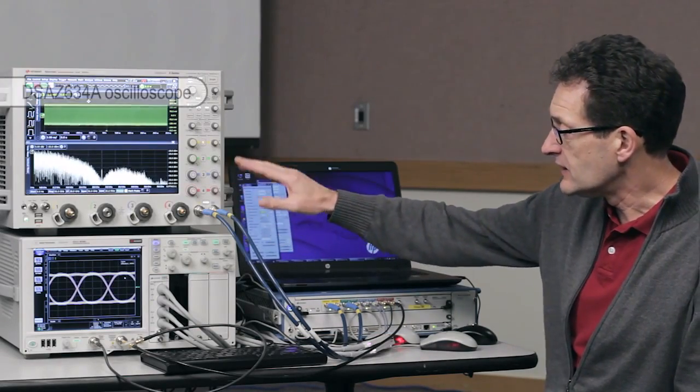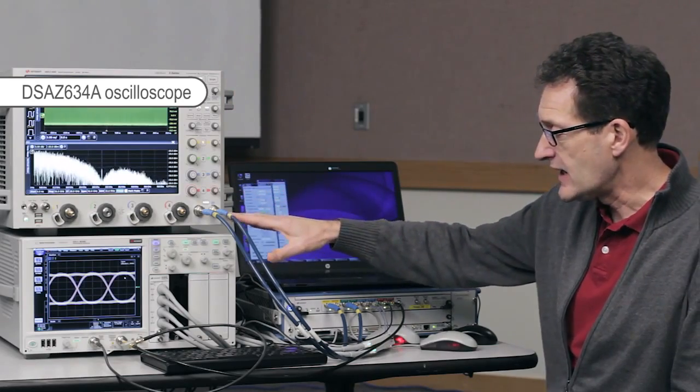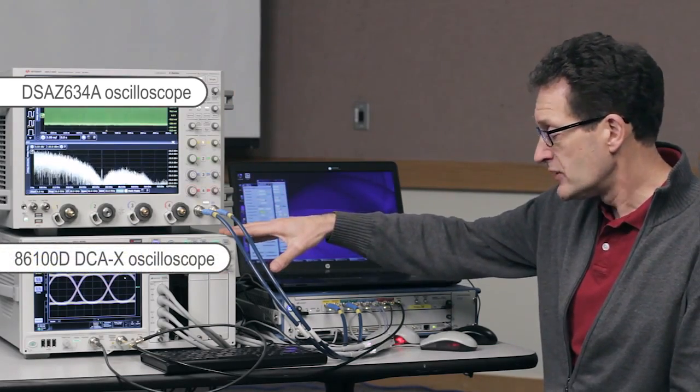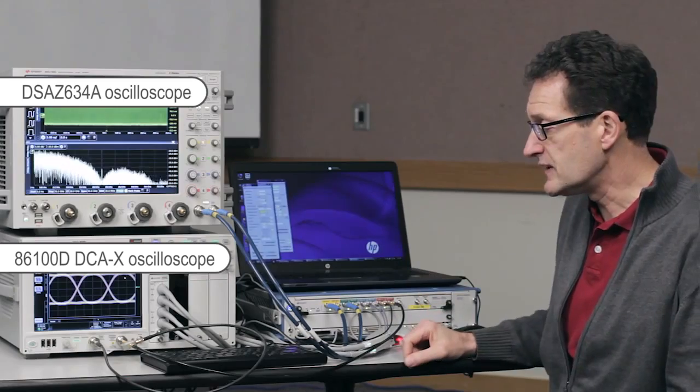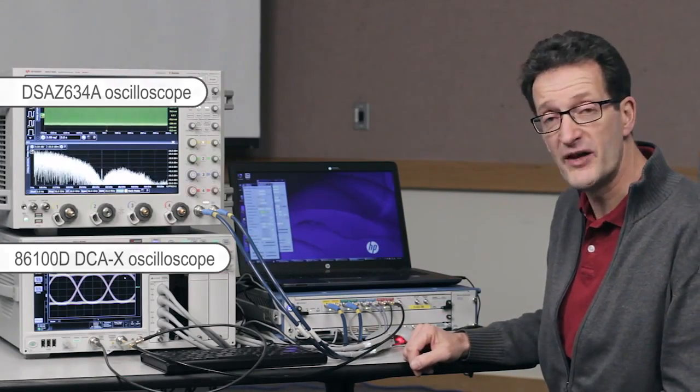For my measurements today, I have it hooked up to both a real-time oscilloscope, that's one of our 63 gigahertz oscilloscopes, and I have another channel hooked up to the DCA-X, in order to show you some eye diagrams with PAM4 measurements.